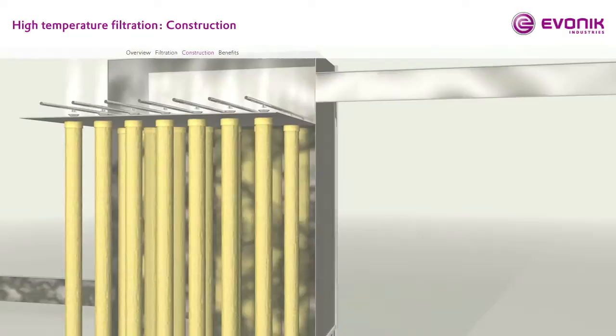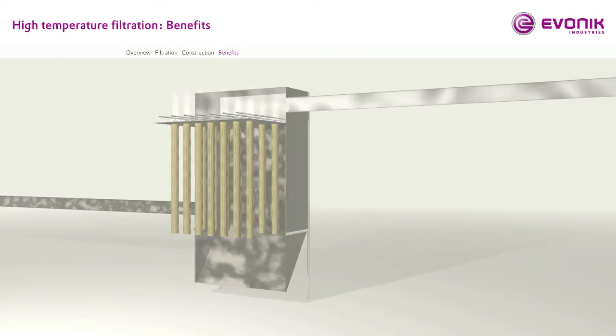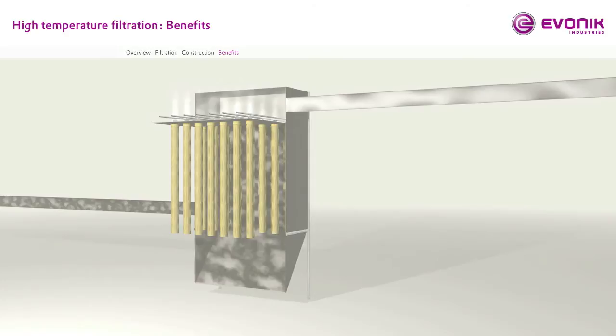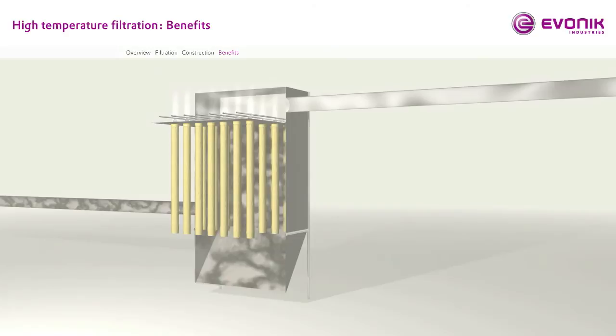Benefits: Suitable for a wide range of flue gas compositions. High temperature stability. Best filtration efficiency up to air-to-cloth ratios of 1.4 meters per minute. Not susceptible against mechanical stress during packing, installation, and operation. Tailor-made products according to customer needs. Highest efficiency even at extreme dust loads of more than 500 grams per cubic meter. No negative influence when using alternative fuels. Suitable for standard cages. No delamination of the filter fabric. Long cycle times and low pressure drop due to advanced filtration performance.